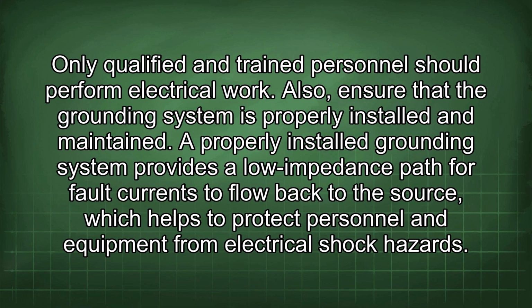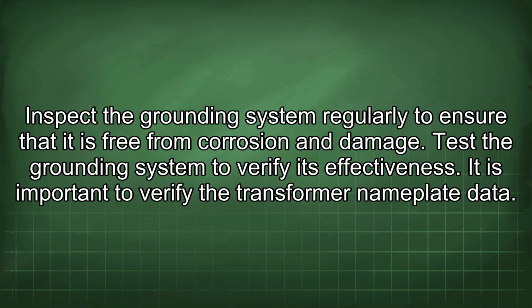A properly installed grounding system provides a low impedance path for fault currents to flow back to the source, which helps to protect personnel and equipment from electrical shock hazards. Inspect the grounding system regularly to ensure that it is free from corrosion and damage. Test the grounding system to verify its effectiveness.